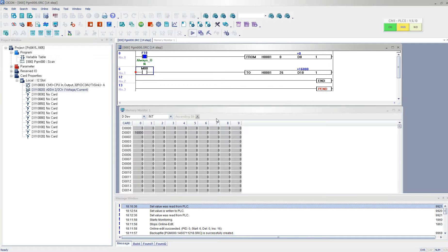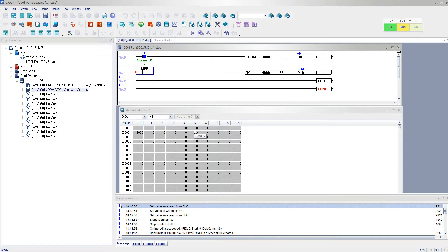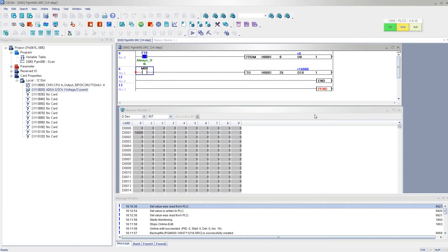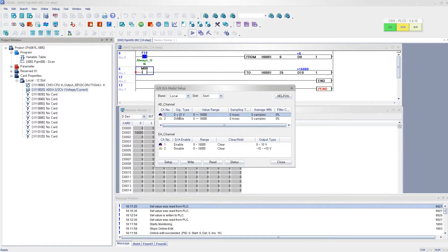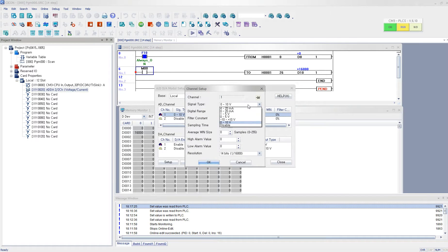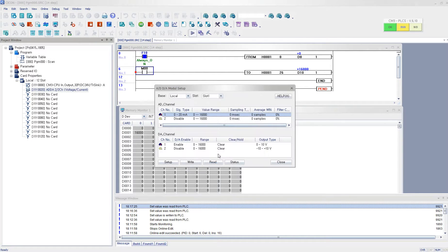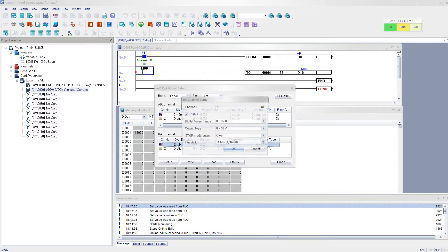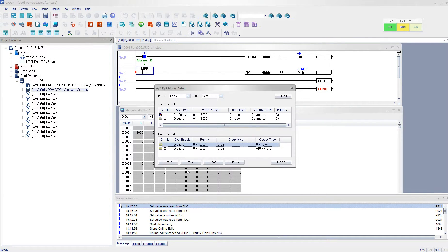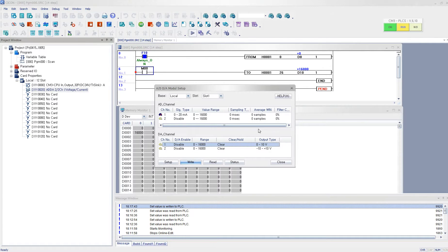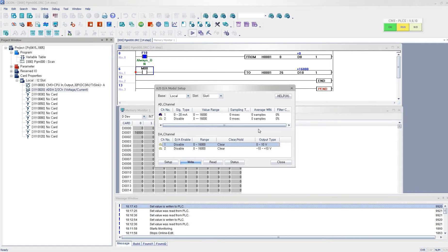Okay, now I am going to switch to the current. So I go ahead and configure my type as 0 to 20 mA digital range, same as it is. Disable it for right now, and I click write it. And I am going to, using my calibrator, I am going to input current.